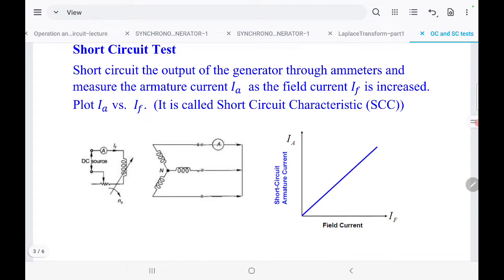Now for the short circuit test: we short circuit the stator terminals, so the resistance is effectively zero and the current will be high. We again change the field current by adjusting the rheostat, so IF changes and EF changes. To measure the current we place an ammeter in series in one line, and it will measure the short circuit current.